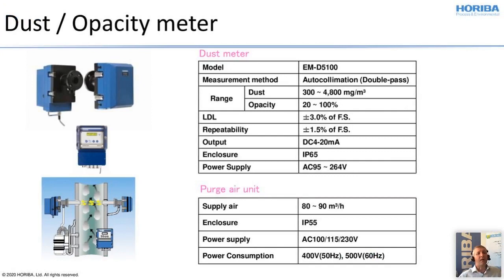I wanted to add some slides for the dust analysis, because this is also an important part. We can also offer you a dust and opacity meter called EMD5100. That is a pass-through detector and can measure, as already mentioned, dust directly or opacity between 0 and 100%. The instrument needs a purge unit to keep the hot gas from the stack away from the electronics. This purge unit is part of the delivery of this opacity dust meter.